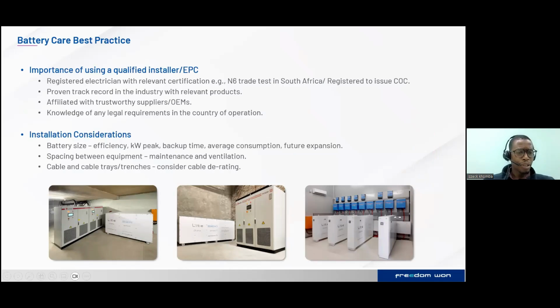So there are also some other installation considerations that we need to keep in mind. The battery sizing. Batteries need to be sized correctly for the particular application. When we look at battery sizing, when we're scaling up to industrial and commercial use, it's much more beneficial to use high voltage batteries, which improves efficiency and also reduces the cost in terms of the required copper to integrate the system. Looking at the kilowatt peak, your backup time, average consumption, and your future expansion. When the battery is sized correctly, you know that whatever load you are powering, you've got sufficient capacity to cater for the kilowatt peak.